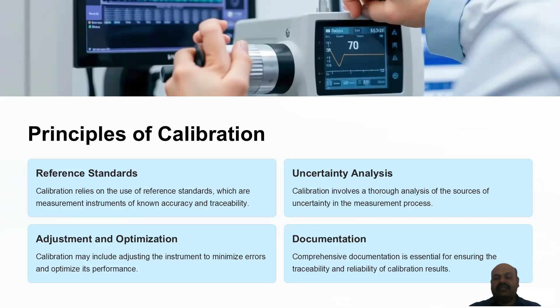Whenever you go for any instrument calibration, we have a sticker pasted on the instrument with color codes. For example, the instrument has to be calibrated once every 3 months. So January to March will have one color code, and April to June will have another color code.